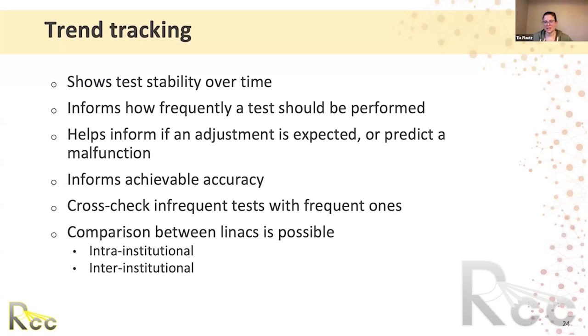Your testing frequency should also be informed by the severity of the result of it failing and not knowing it failed.